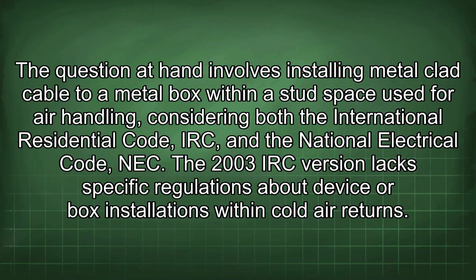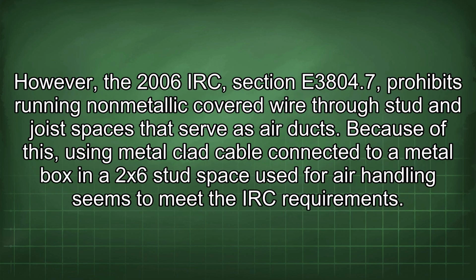The question at hand involves installing metal-clad cable to a metal box within a stud space used for air handling, considering both the International Residential Code (IRC) and the National Electrical Code (NEC). The 2003 IRC version lacks specific regulations about device or box installations within cold air returns. However, the 2006 IRC, Section E3804.7, prohibits running non-metallic covered wire through stud and joist spaces that serve as air ducts. Because of this, using metal-clad cable connected to a metal box in a 2x6 stud space used for air handling seems to meet the IRC requirements.